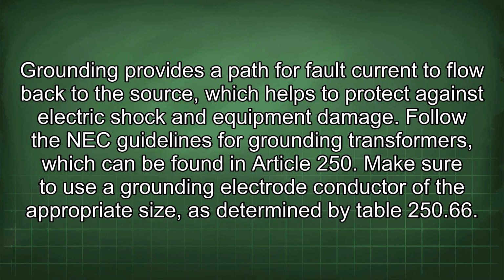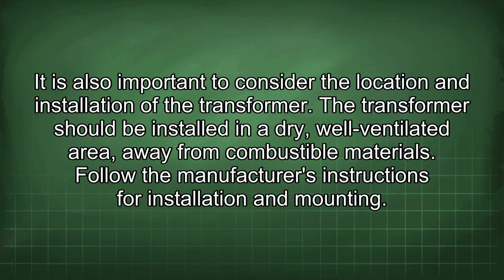Follow the NEC guidelines for grounding transformers, which can be found in Article 250. Make sure to use a grounding electrode conductor of the appropriate size, as determined by Table 250.66. It is also important to consider the location and installation of the transformer. The transformer should be installed in a dry, well-ventilated area, away from combustible materials.